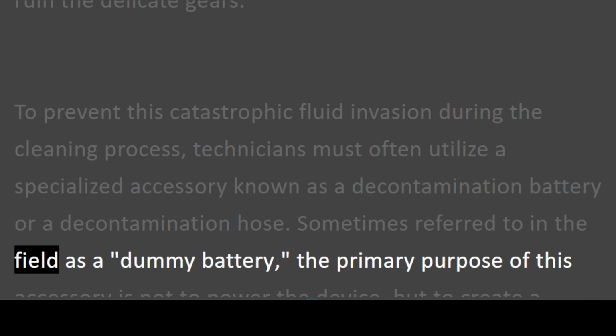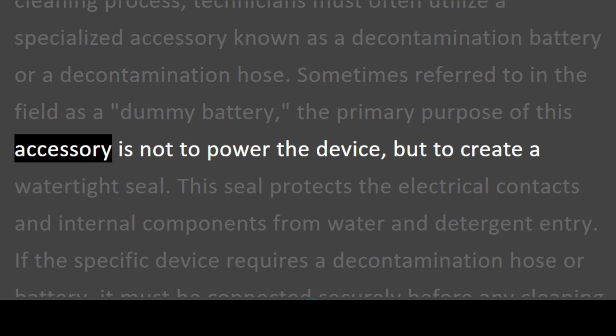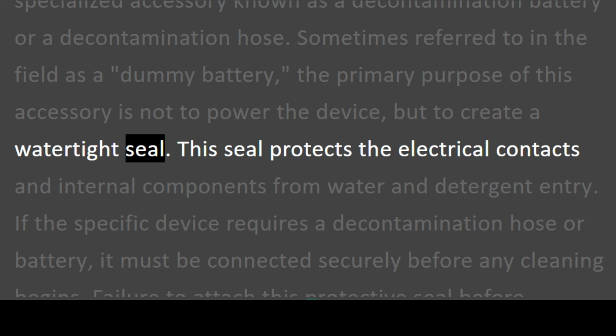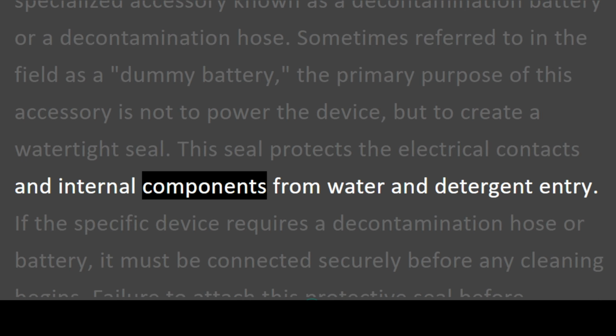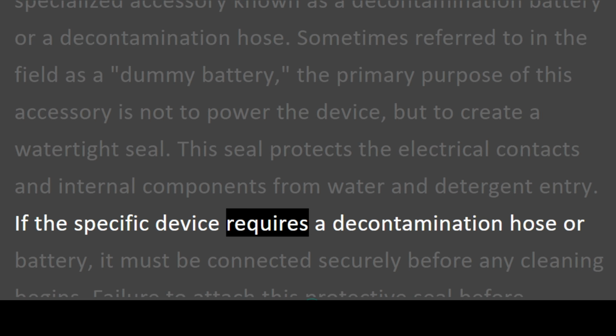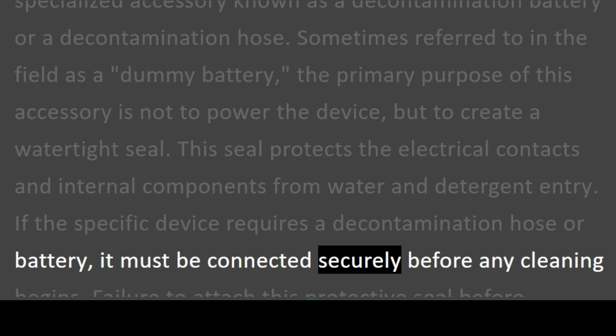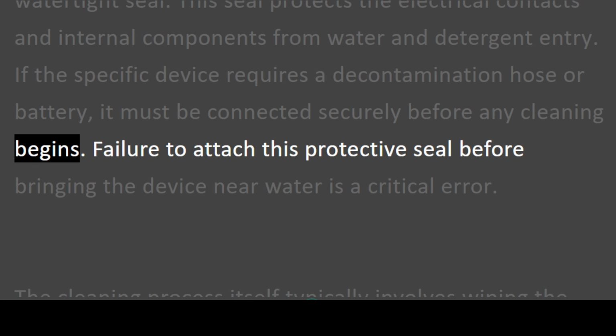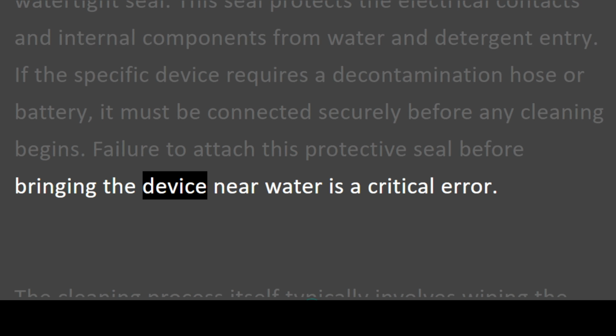Sometimes referred to in the field as a dummy battery, the primary purpose of this accessory is not to power the device, but to create a watertight seal. This seal protects the electrical contacts and internal components from water and detergent entry. If the specific device requires a decontamination hose or battery, it must be connected securely before any cleaning begins. Failure to attach this protective seal before bringing the device near water is a critical error.